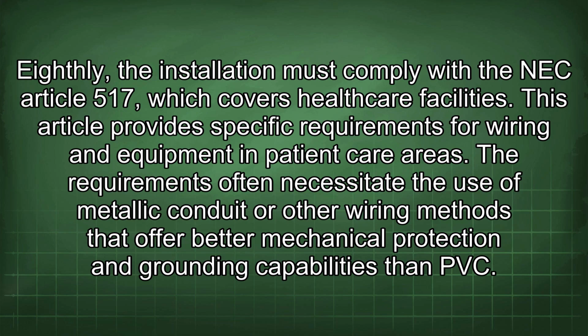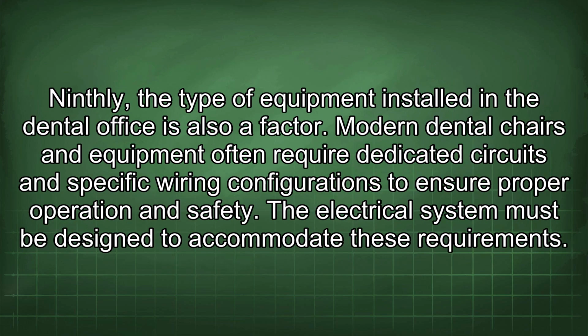Eighthly, the installation must comply with NEC Article 517, which covers healthcare facilities. This article provides specific requirements for wiring and equipment in patient care areas. The requirements often necessitate the use of metallic conduit or other wiring methods that offer better mechanical protection and grounding capabilities than PVC. Ninthly, the type of equipment installed in the dental office is also a factor. Modern dental chairs and equipment often require dedicated circuits and specific wiring configurations to ensure proper operation and safety. The electrical system must be designed to accommodate these requirements.